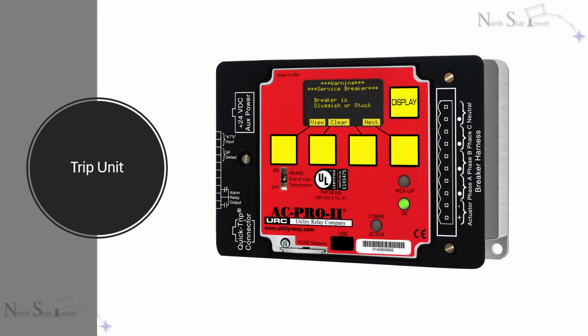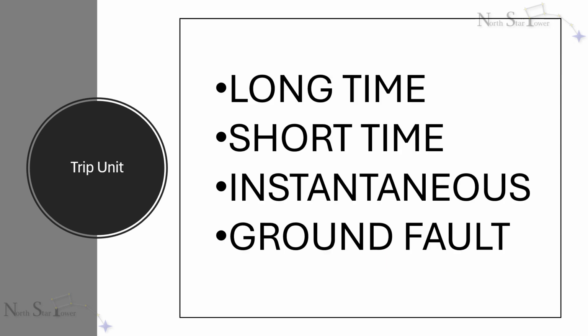The four key trip functions are long time delay, which protects against sustained overloads. It allows minor overcurrents to persist briefly, but trips before the system overheats. Short time delay allows short bursts of high current from things like motor startups, but trips quickly if those currents continue too long. Instantaneous trip provides immediate protection if current spikes to dangerous levels, like during a direct short. Ground fault detects current leakage outside the intended path, a key protection against fire and shock risks.